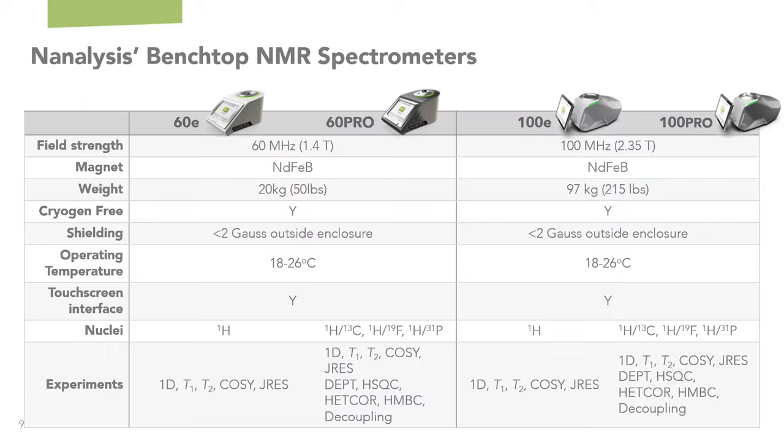Nanalysis has two main product lines: our 60 MHz and our 100 MHz. Both are neodymium iron boron-based magnets, so they're cryogen-free with very limited stray field, making them easier to site and safer to be around. They require standard operating lab conditions and can all be controlled through a touchscreen interface, but both have application programmatic interfaces for remote control. We have a proton-only model for routine analysis and multinuclear-based systems for those who require it. They come preloaded with common structure elucidation experiments and have advanced programming interfaces for more complex or custom pulse programs.